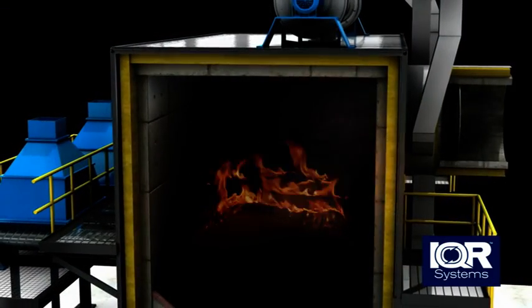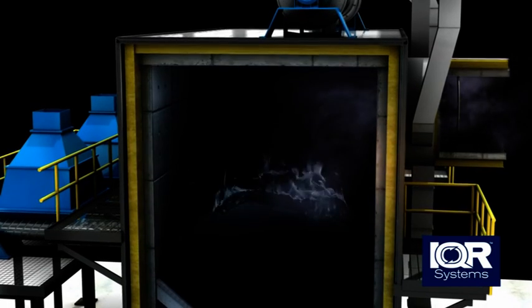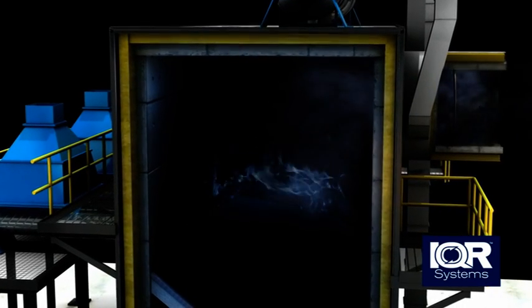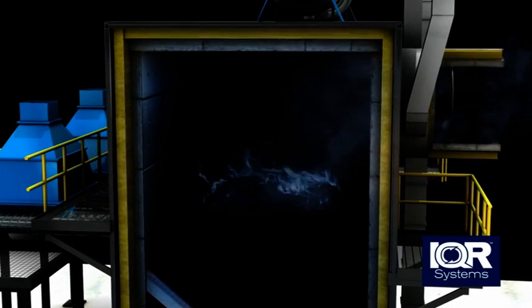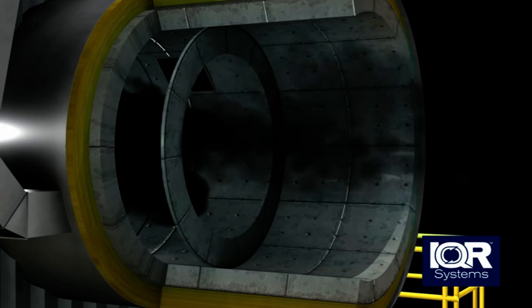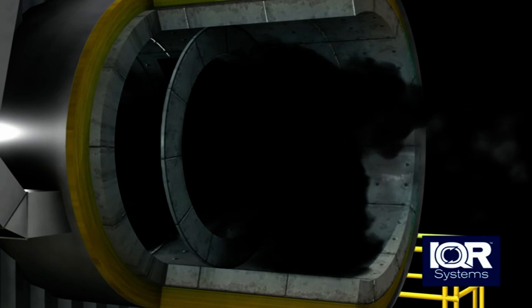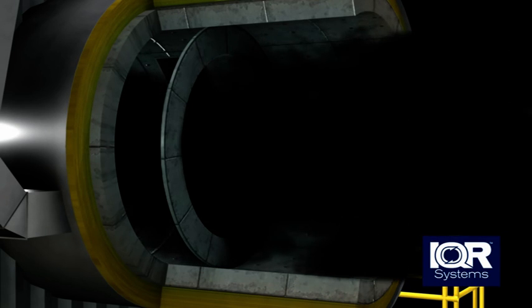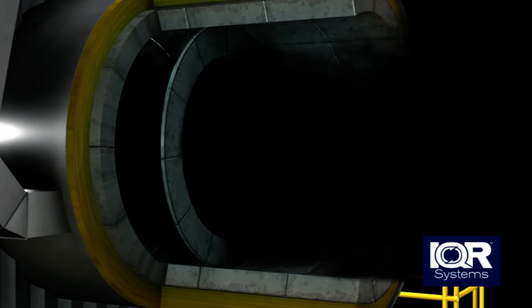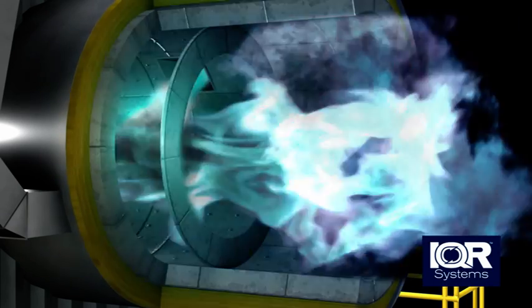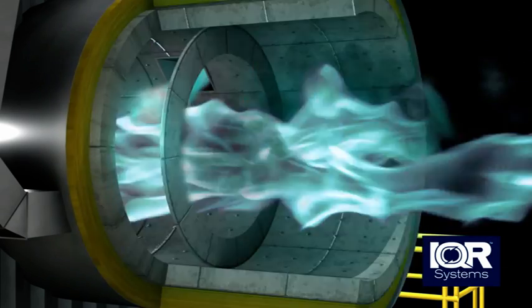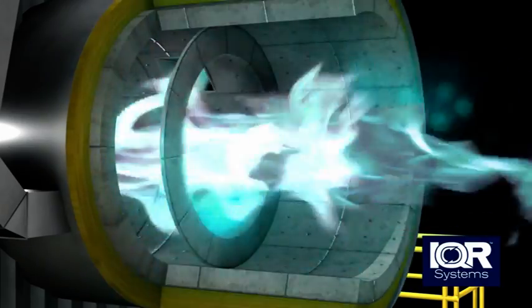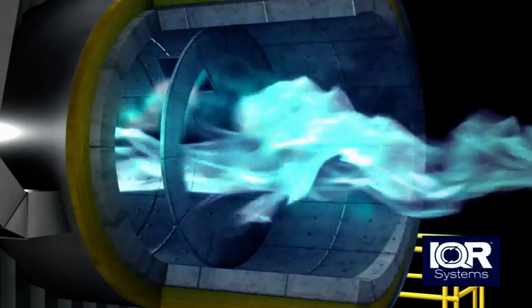By adjusting the oxygen levels using the fans, the open flames in the gasifier die and the gasification process starts. The gas that is produced in the gasification process passes through the burner, where the secondary air is added in order to ignite the combustible gas. Gasification and combustion now take place in two separate and controlled steps.